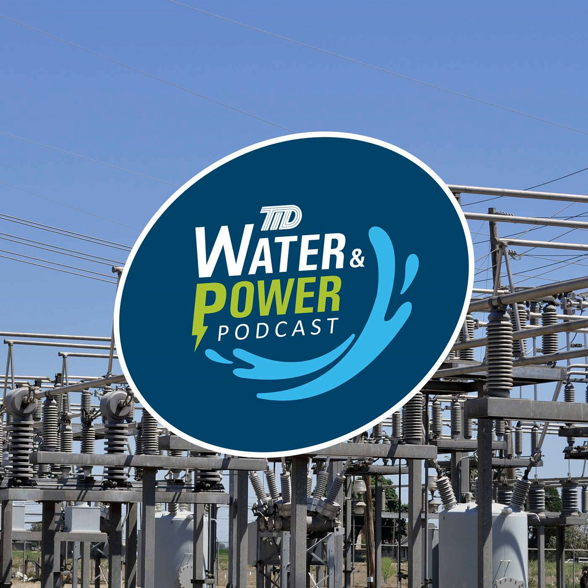Okay. Now, speaking of kind of the monitoring and knowing, the system being able to report kind of what's coming in and going out, how does that all work? Is there somebody who's monitoring that power that's coming in and going out? How do we know when there is a fault somewhere in the substation? So I think that's kind of a two-part question. We do have someone who's physically monitoring for alarm conditions where, let's say, if your bus is supposed to be operating at this voltage, but you see that it is dropping down or exceeding that voltage, there's alarm set points that are programmed in that will alarm in the power control center. Same thing with current.